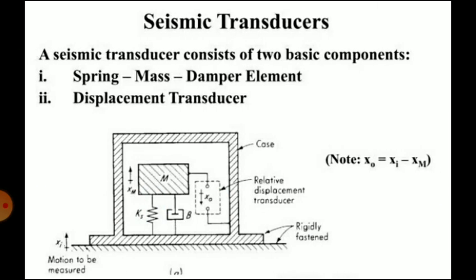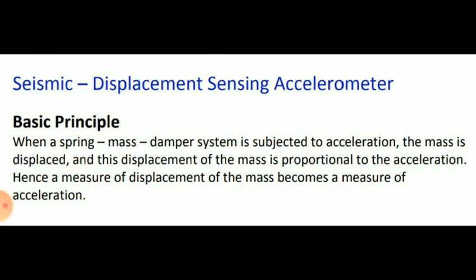So, we will discuss the seismic transducer. The seismic transducer consists of two basic components. First is the spring mass damper element and second is the displacement transducer. The basic principle of a seismic or displacement sensing accelerometer: when the spring mass damper system is subjected to acceleration, the mass is displaced and this displacement of the mass is proportional to the acceleration. Hence, a measure of displacement of the mass becomes a measure of acceleration.